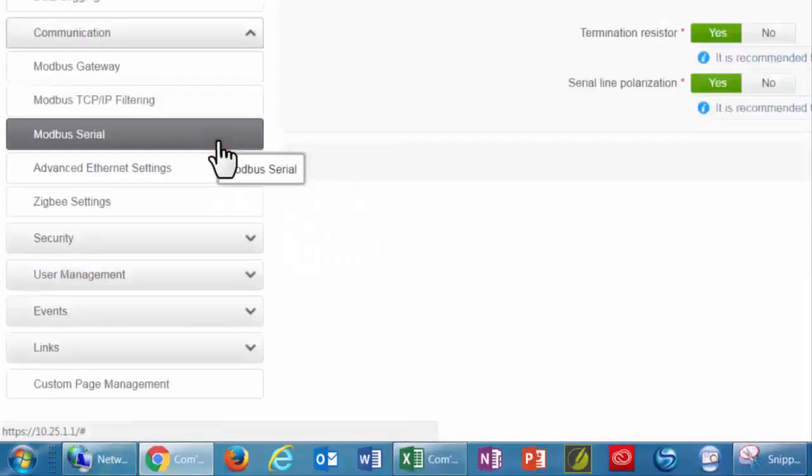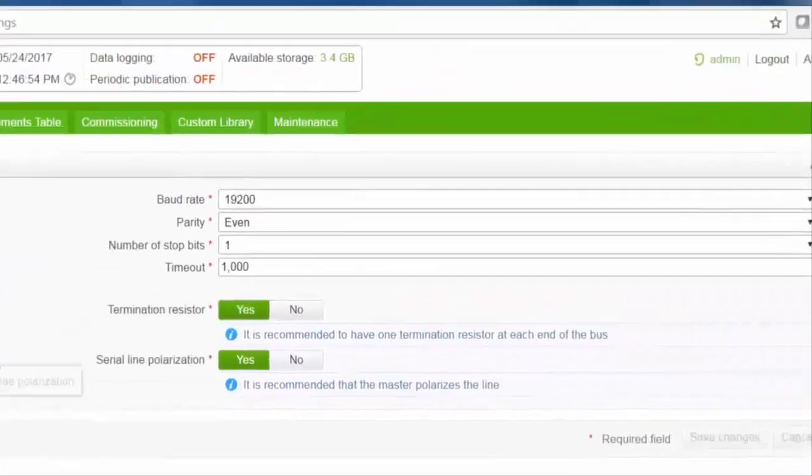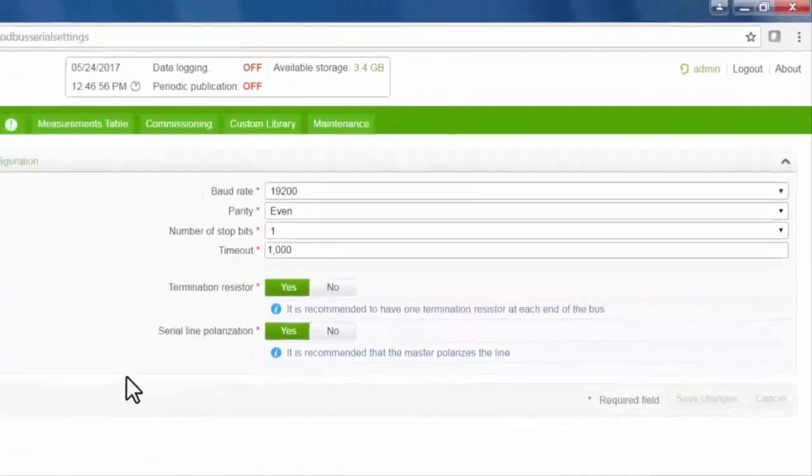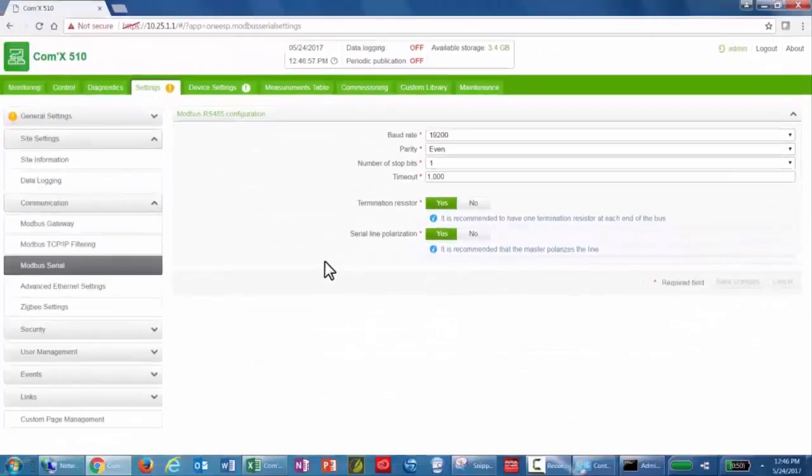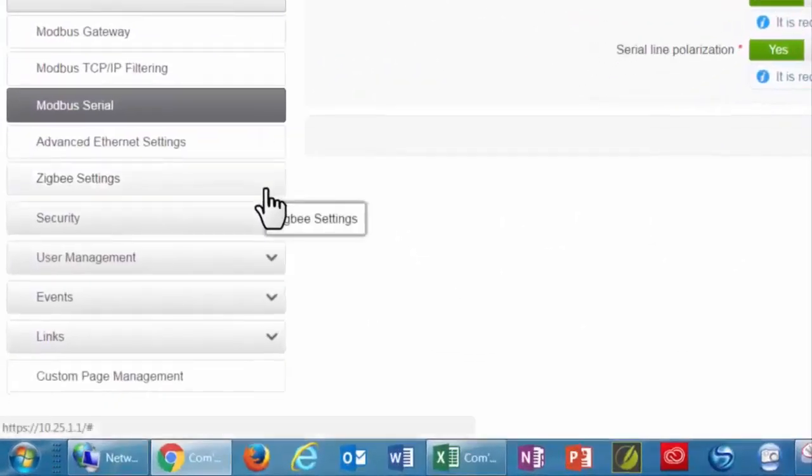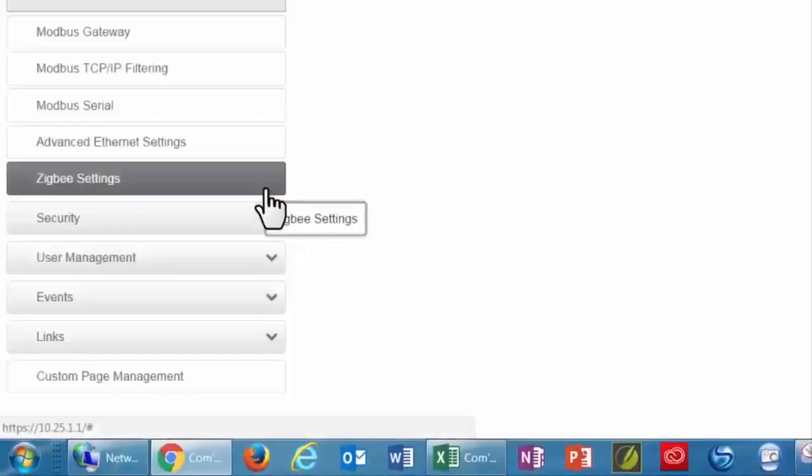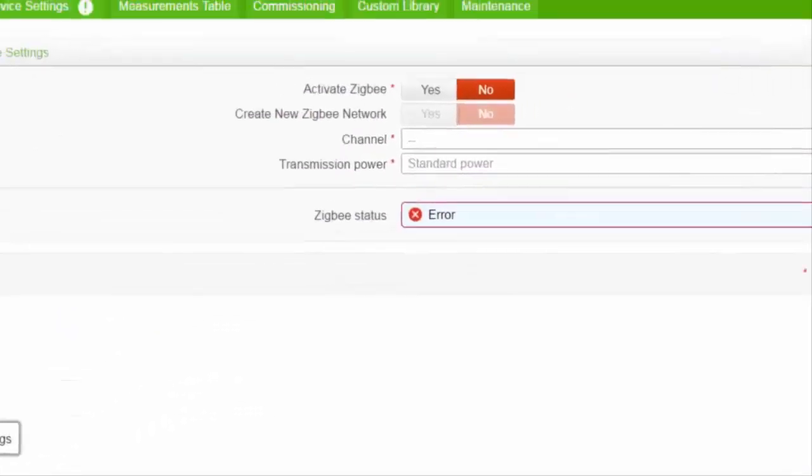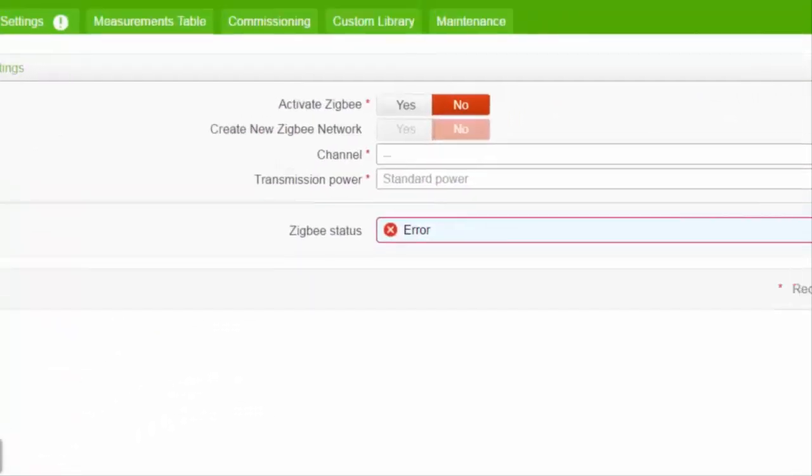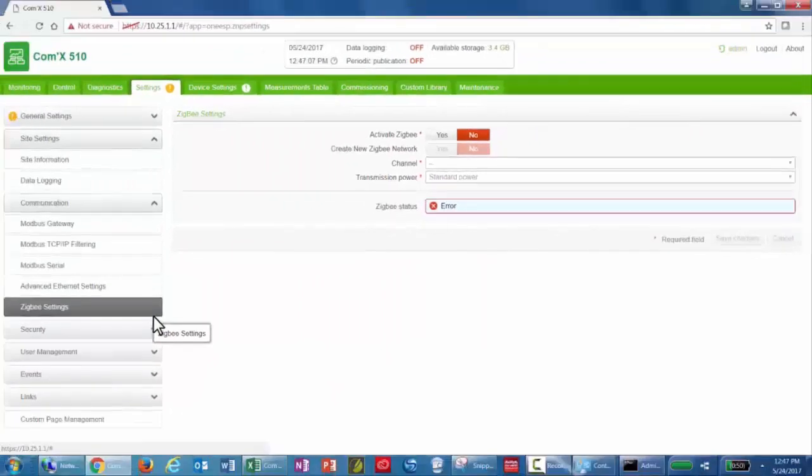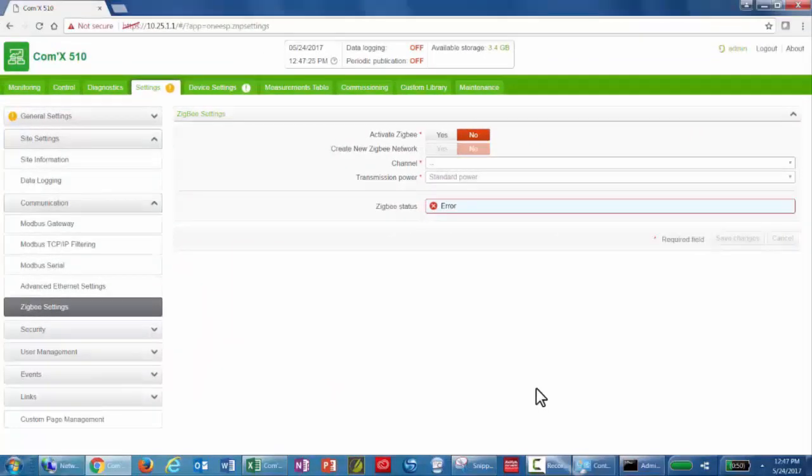Next, verify the Modbus serial settings correspond to the meters connected to the Com'X serial port. If ZigBee devices are included in the architecture, activate ZigBee and create a new ZigBee network. Select the transmission power based on the location of the ZigBee dongle.